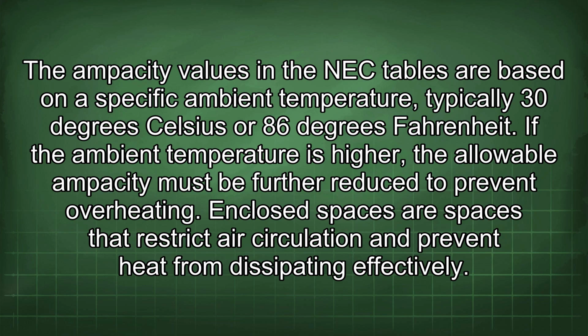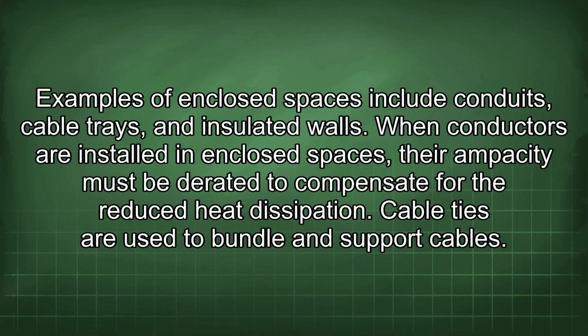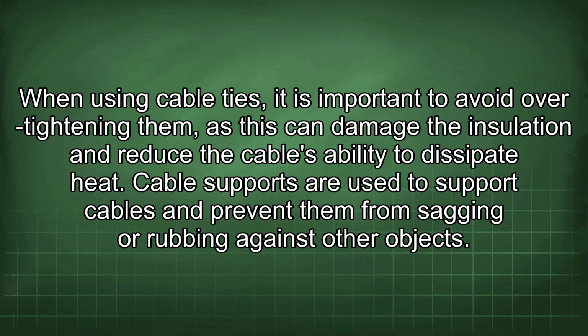Enclosed spaces are spaces that restrict air circulation and prevent heat from dissipating effectively. Examples of enclosed spaces include conduits, cable trays, and insulated walls. When conductors are installed in enclosed spaces, their ampacity must be derated to compensate for the reduced heat dissipation. Cable ties are used to bundle and support cables. When using cable ties, it is important to avoid over-tightening them, as this can damage the insulation and reduce the cable's ability to dissipate heat.